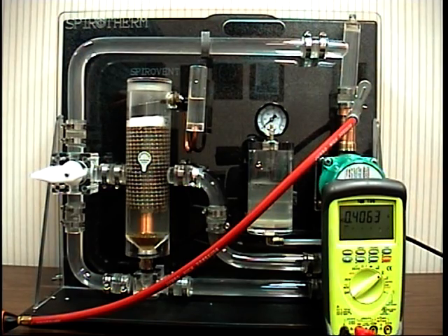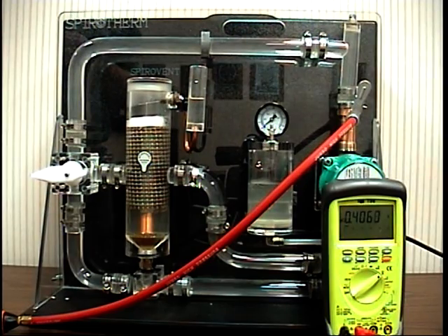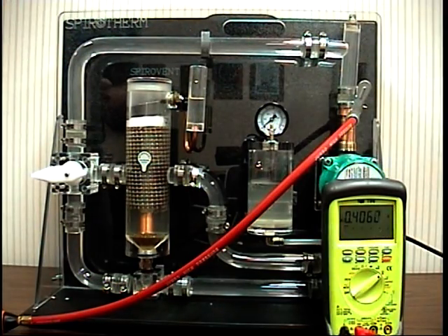A typical hydronic heating system can contain three different types of air. The first one is free air, the air that might be contained at high points in the system that you can manually bleed out. The next type is entrained air, the air that flows with the water itself. The third type is dissolved air, the air that the fish breathe. You can't actually see it, but it's there.